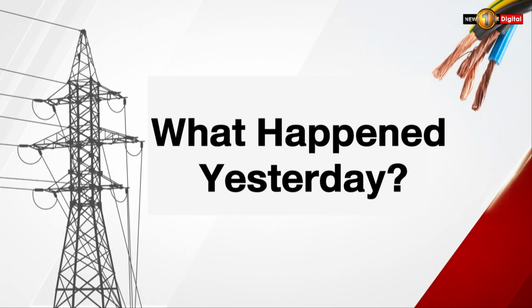What happened yesterday? According to data available on the CEB website, the reduction in power generation began around 6:45 am yesterday. By 7:30 am, the Norochcholai coal power plant was supplying its maximum capacity of 812 megawatts to the national grid. However, from 7:30 am onwards, the plant's output was gradually reduced, and by 11 am, it was supplying only 473 megawatts. Other thermal power plants also reduced their output during this period.